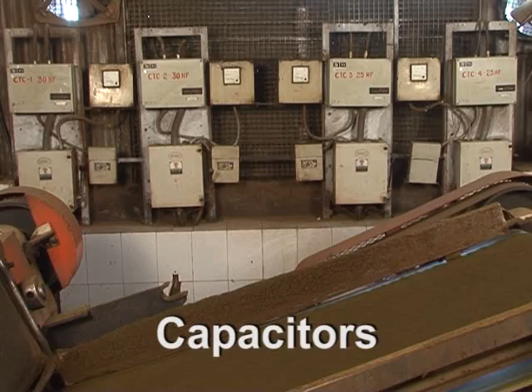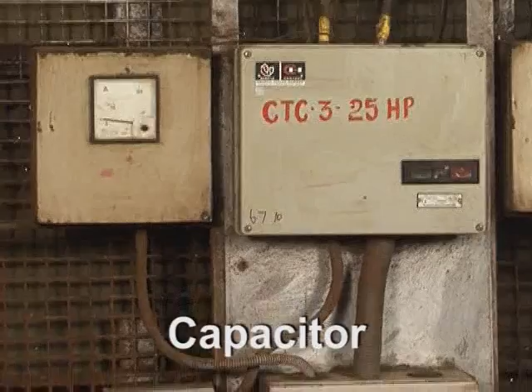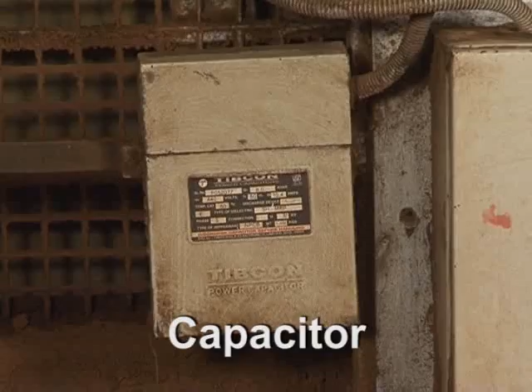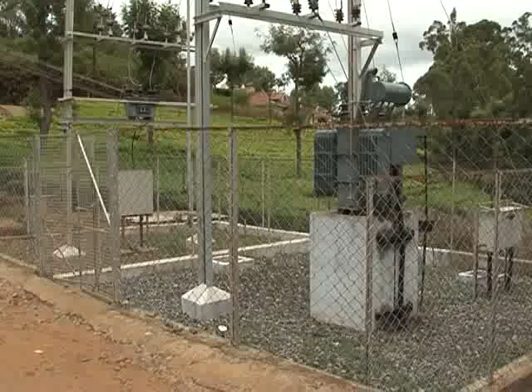Thanks to technology, we have a device called a capacitor to control power factor or to improve the power factor. Capacitor is a device that stores charge and releases to compensate the surge in kVAR. The kVA or demand, which is fixed given by the energy supplying authorities, needs to be controlled at a particular level for two reasons. Number one is that it is a fixed one by the energy supplying authority. Every factory needs to pay a demand charge for each kVA sanctioned to the industry. Secondly, for escalating or exceeding this kVA, one has to incur a penalty.